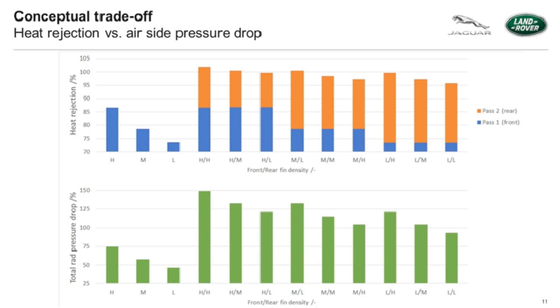The first graph on the y-axis is looking at heat rejection as a percentage of the heat rejection required for maximum fuel cell power. And on the second graph at the bottom, we're looking at the pressure drop as a percentage of the maximum pressure capability of the fan, and that's under ideal conditions. So it's a simple setup, no ram air effect and no airside blockages. It's a conceptual trade-off. So again, we're using this to illustrate qualitatively the relationship between airside heat rejection performance and pressure drop.